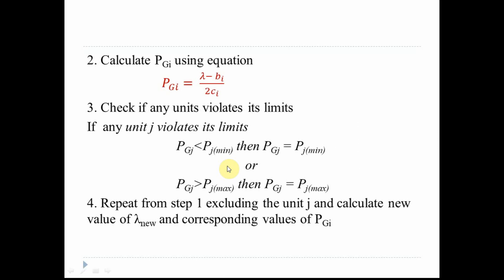Suppose unit J is violating its limit. Violation can be of two types: PGJ can be less than the minimum limit, or it can be greater than the maximum limit. If the scheduled generation goes below the minimum limit, we peg or fix that unit's generation to its minimum value. For example, if a unit has a limit of 50 to 100 MW and the calculated value is 20 MW, we fix the generation to 50 MW.